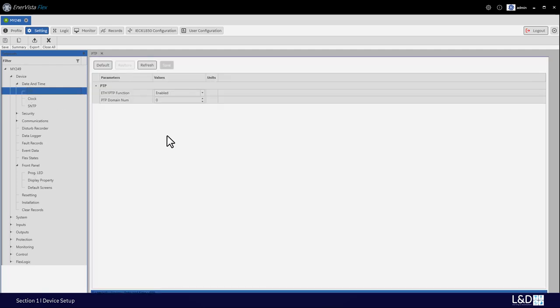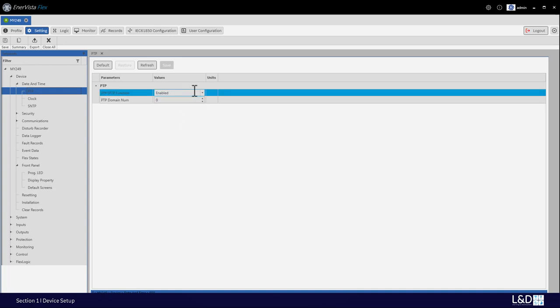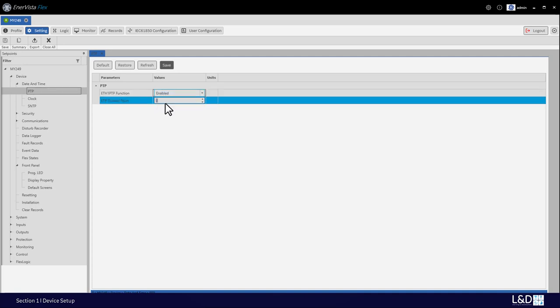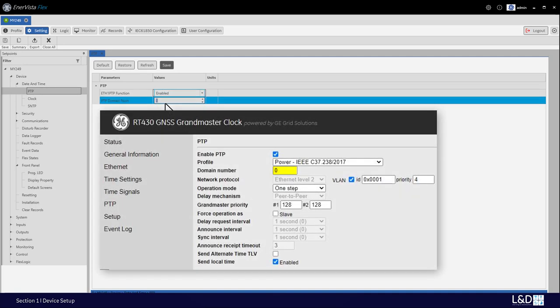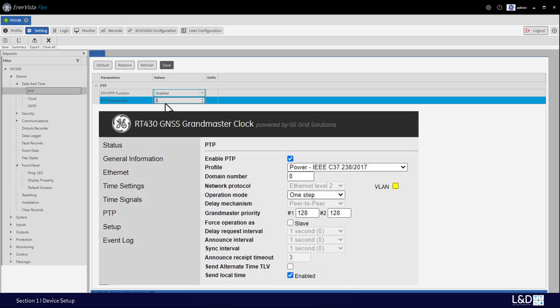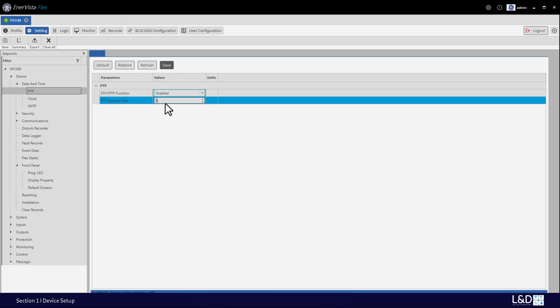PTP clock is a new setting from version 2. We can enable PTP here and make sure that the domain setting should match the domain setting from the clock, for example the RT430 clock. Because P40 RGL Enhanced does not support VLAN, the VLAN setting should be unchecked. P40 RGL supports IEEE C37.238 and IEC 61850 9-3 PTP protocols.